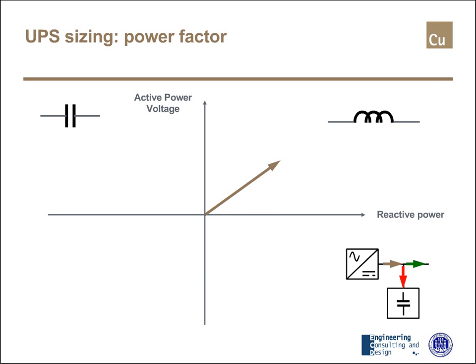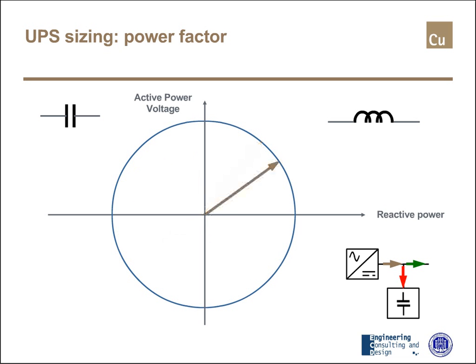The maximum current that can be managed by the UPS electronics has no limit in phase displacement. With reference to the inverter, in the plane of active power and reactive power, the working range is a circle like the blue one shown. But the phase displacement of the filter current is fixed because the filter is basically a capacitor, so the difference between these two currents is fixed.